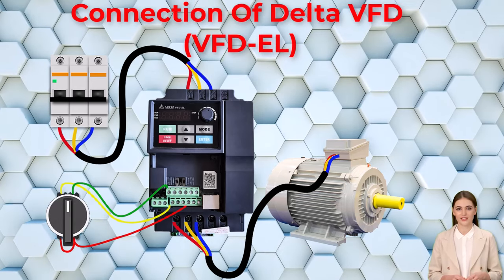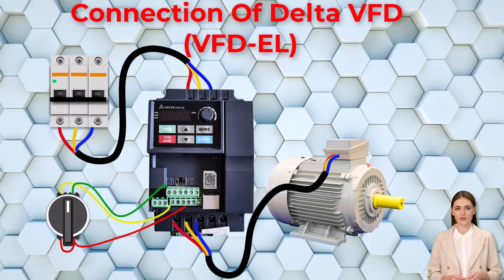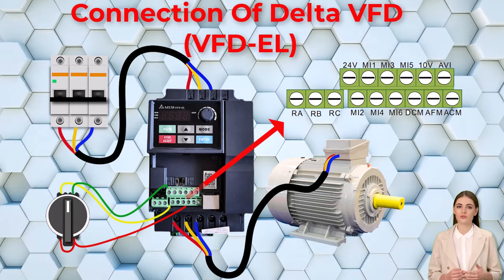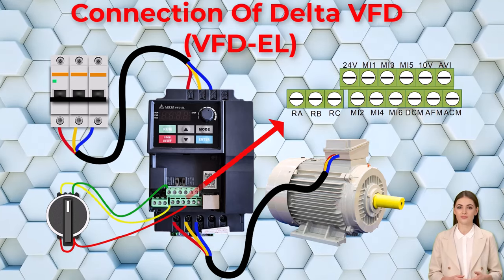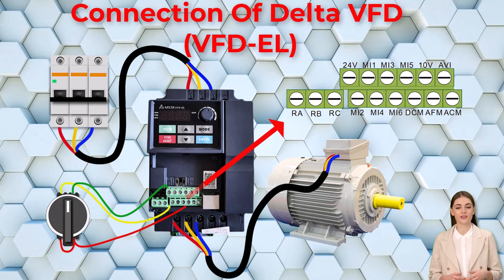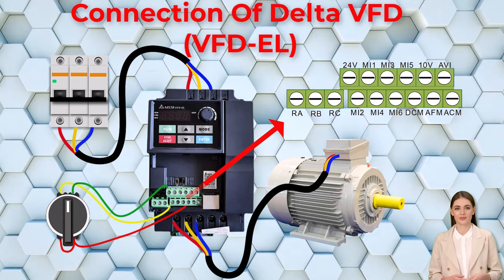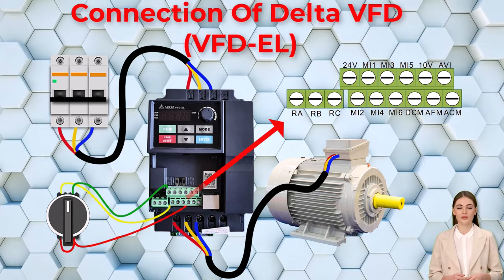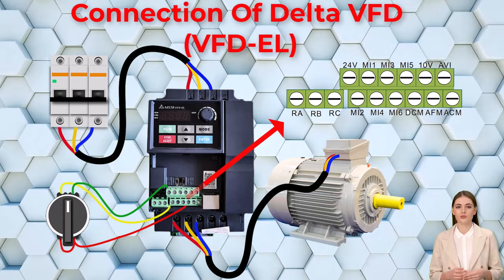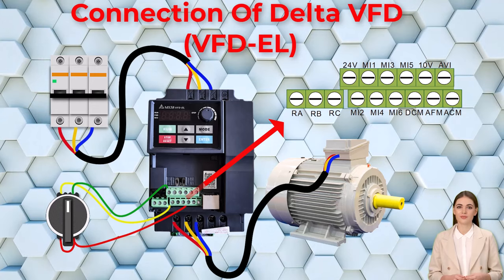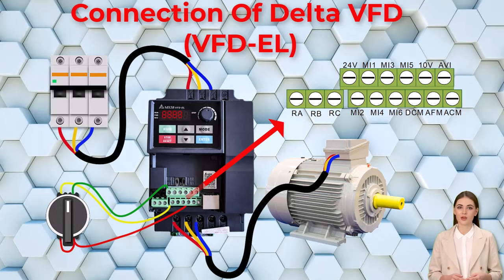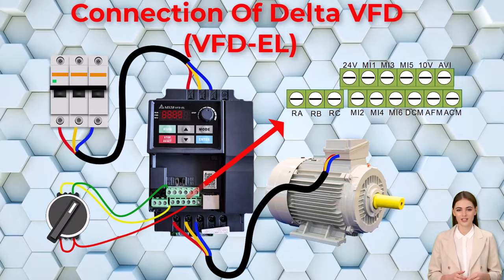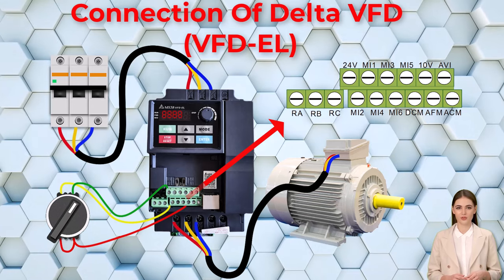Next, connect a selector switch to turn the motor on and off in both forward and reverse directions. Looking at the control connection in the catalog: DCM is common, MI1 is for forward, and MI2 is for reverse. Make the connections by following these instructions, then test the connection in both forward and reverse.